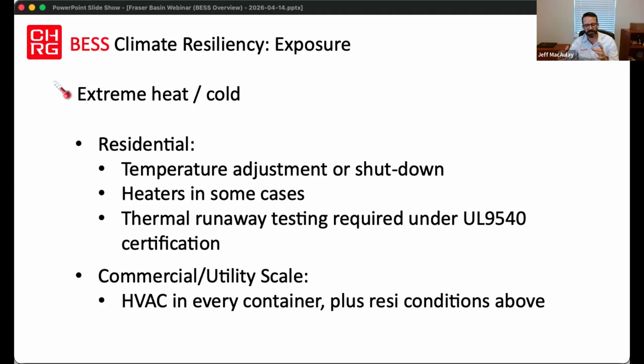If the software is not shutting it down, and you have a thermal event at some part of the battery overall enclosure, then these things are tested so that the fire doesn't propagate within the enclosure.